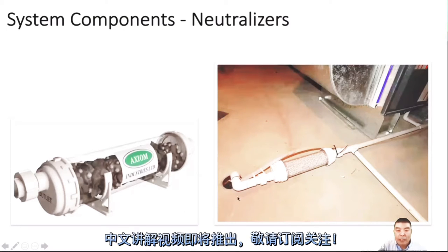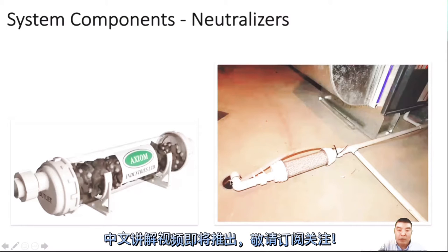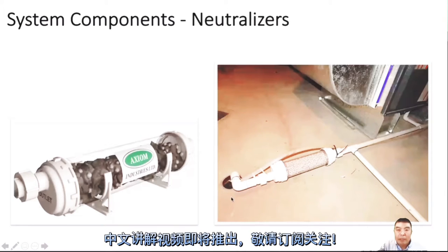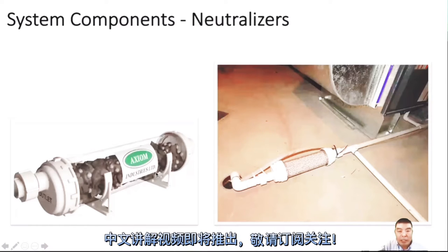Some houses have copper pipes, and if you always drain the condensate water into them it will damage the pipe. Not all provinces have this requirement, but we should know about it. If you look at the neutralizer media and the color has changed, it needs to be replaced.